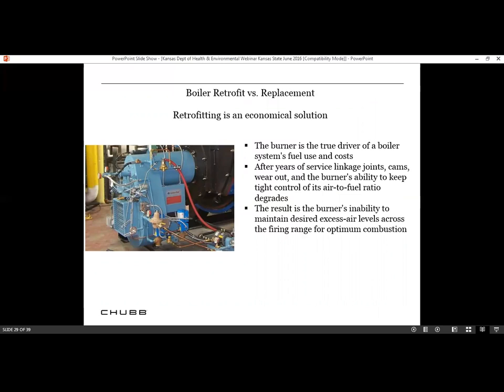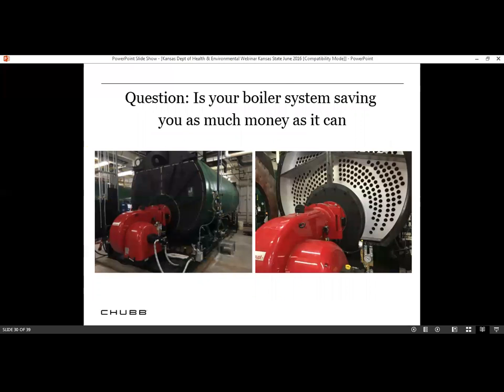As far as boiler retrofit versus replacement, the burner is the true driver of the boiler system. Fuel cost, and after years of service, the linkage, the joints, cams wear out, and the burner's ability to keep tight control of the fuel-to-air ratio degrades. So if you look at this boiler, this is the new burner that we put into that boiler, the one on the left, and I did an internal inspection. You can see on the picture on the right the tubes. This is a wetback Johnston boiler. It's very large. It's about 25,000 pounds per hour. But I have them paint the tubes with a high temp aluminum so that we can control corrosion and we can see leaks. And actually, that photo there was from last year. So the boiler is pretty clean.